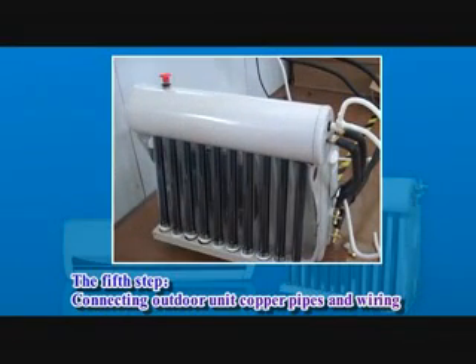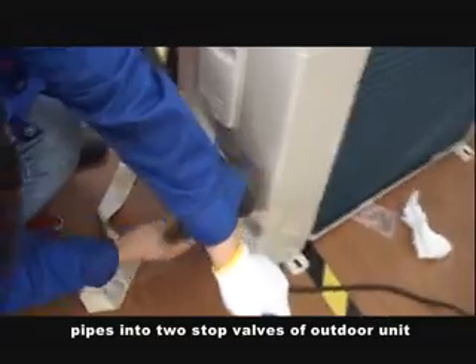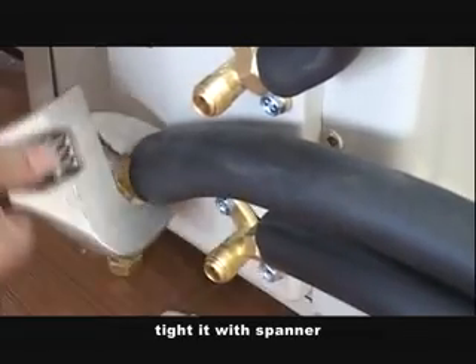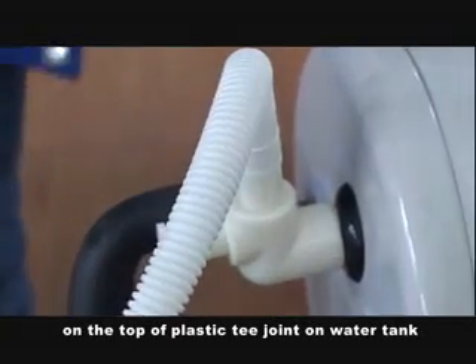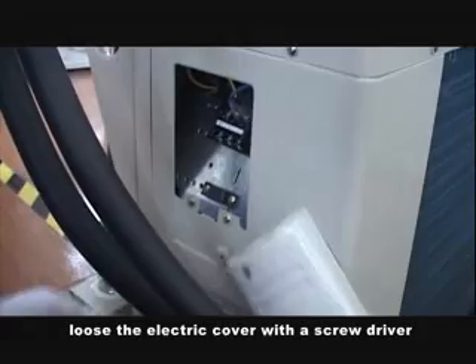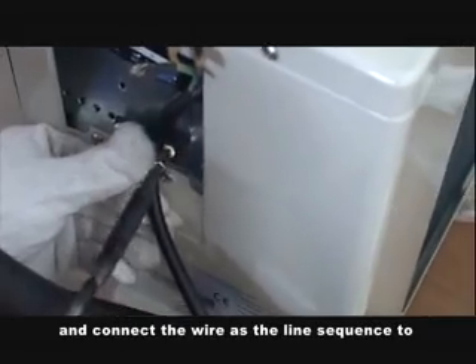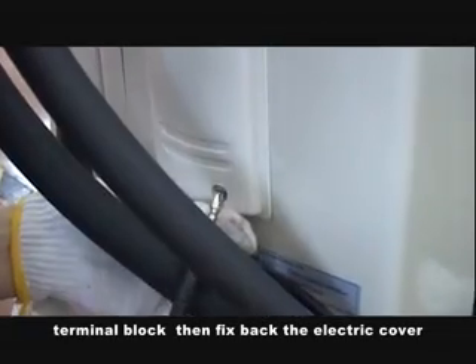Fifth step: connect the outdoor unit copper pipes and wiring. Connect one end of the two connecting pipes into the two stop valves of the outdoor unit and tighten. Connect the tube from the indoor unit to the top of the plastic joint on the water tank, and connect the other tube to the other terminal. Loosen the electric cover with the screwdriver, use the clamp, tie the power wire, and connect the wire in the correct sequence to the terminal block. Then fix back the electric cover.